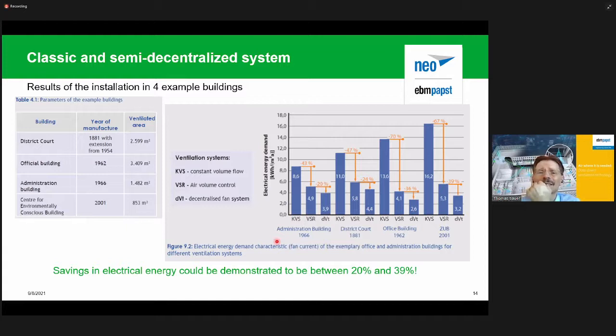What we can see here is a comparison to a classical constant volume flow system. This was calculated, not measured, because there was already an air volume control system in that building. Obviously, most applications as of today are air volume control systems, or VAV systems. But if we use the semi-decentralized system, we can see that there is quite some efficiency to gain. We have demonstrated that to be between 20 and 39% just for the air distribution. That is not counting the energy losses that you have when running those ducts with high pressures and a lot of leakage. We have customers that have 20 to 30% leakages in their system because the buildings might be old and what have you.